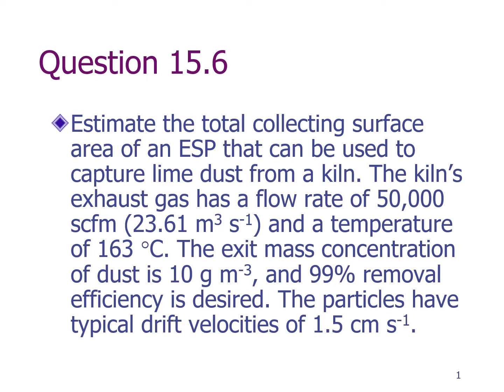This problem calls for the Deutsch-Anderson equation, which tells us the efficiency as a function of drift velocity, flow rate, and area. Notice that we don't actually need the exit mass concentration because the efficiency is 99% and that's all we really need.